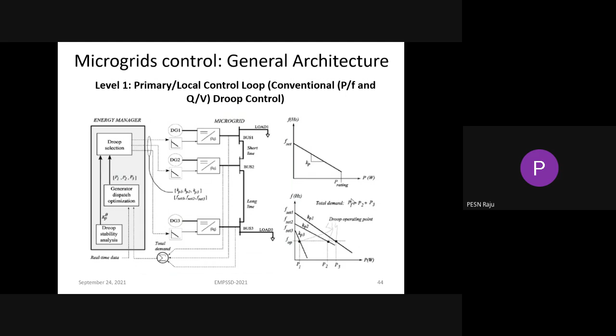It will take the droop stability analysis, and from that it will dispatch the droop gains to all the DGs, and it will optimize the generator dispatch, depending on the power generation inside the microgrid and the total demand in the microgrid. So when we go for the primary local control, droop control, that doesn't require any ICT communication. But when we go for more, it requires partial communication.